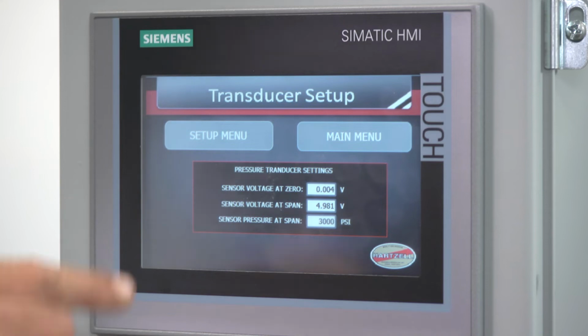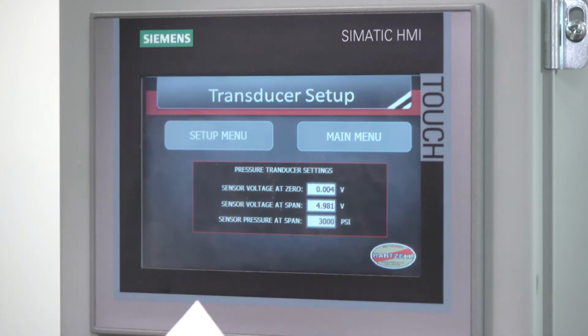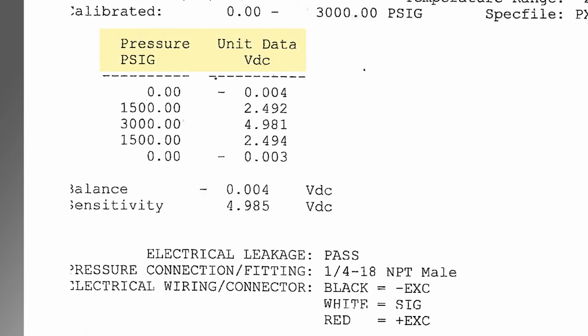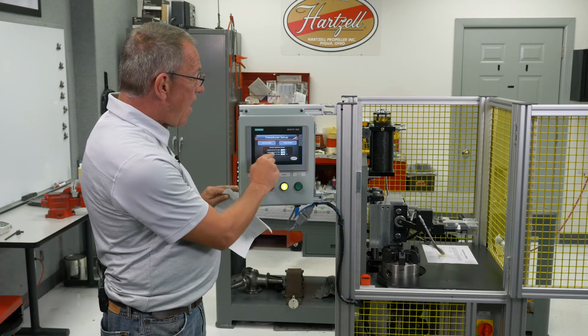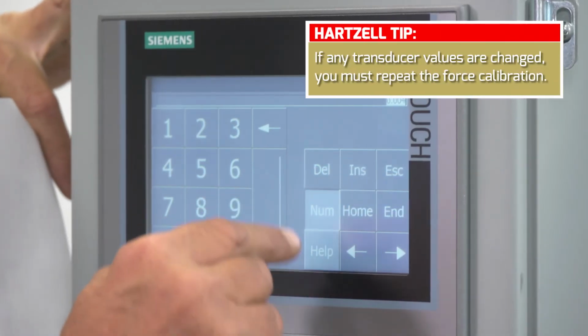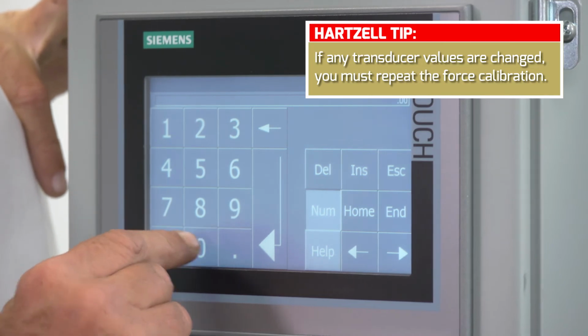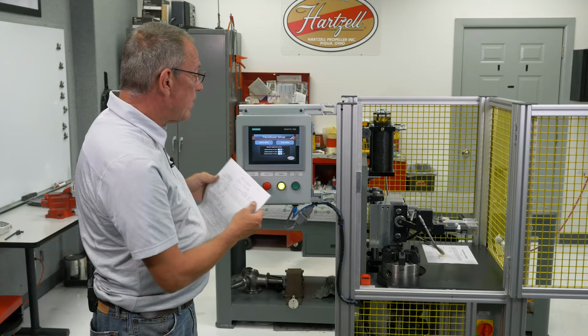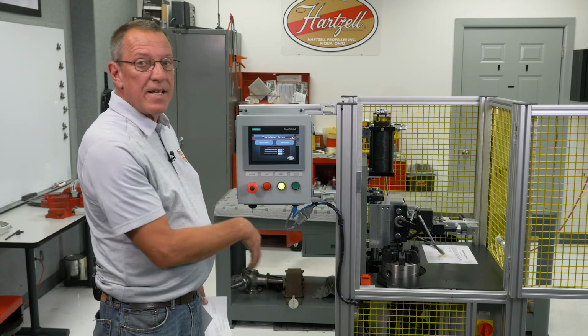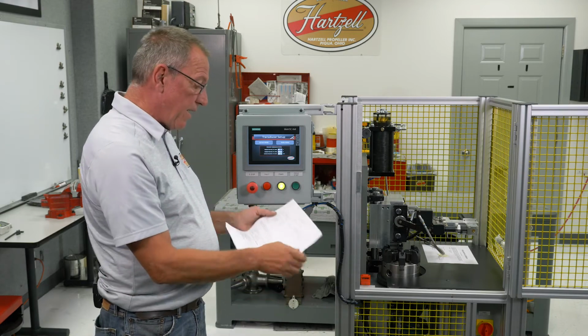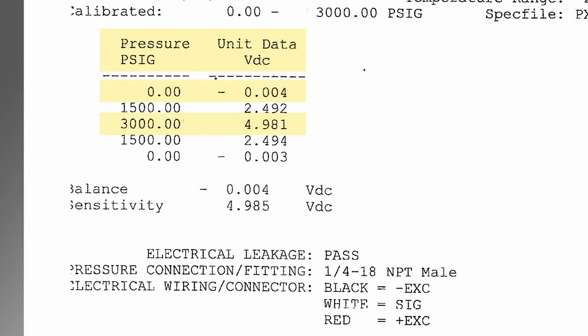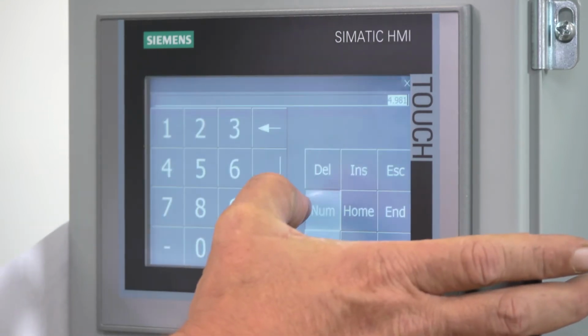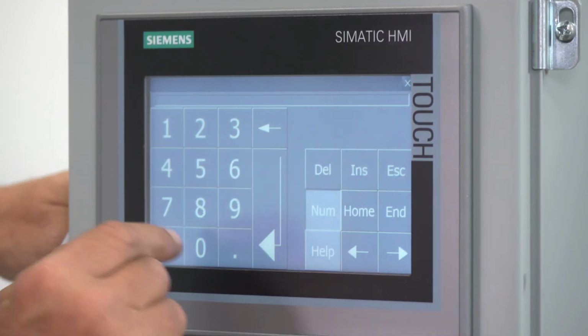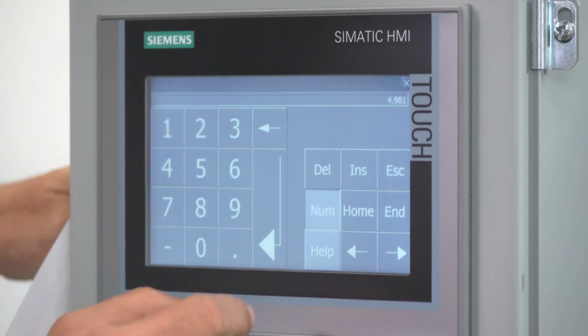So the settings you put in are sensor voltage at 0. On your calibration paperwork, it says pressure PSIG 0 is 0.004 VDC. So I'll change this to 0.004, enter. Sensor voltage at span, that's going to be at the max PSI, 3,000 PSI. So I find on the paperwork at 3,000 PSI, it should be 4.981. So hit here, and I'll put in 4.981. Enter.